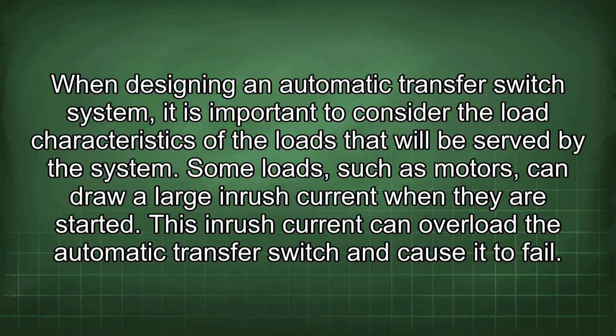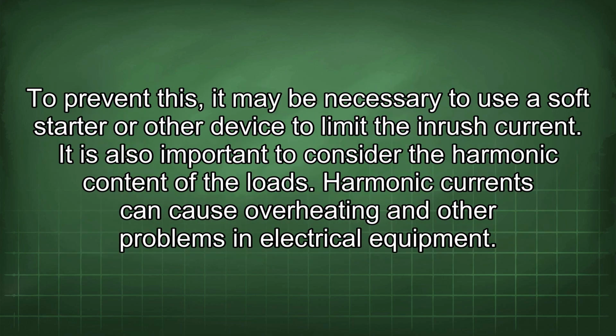When designing an automatic transfer switch system, it is important to consider the load characteristics of the loads that will be served by the system. Some loads, such as motors, can draw a large inrush current when they are started. This inrush current can overload the automatic transfer switch and cause it to fail. To prevent this, it may be necessary to use a soft starter or other device to limit the inrush current.